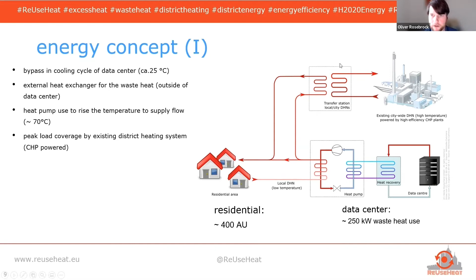If we think about the dimensioning of this heat pump, it was said that it makes sense to cover the base load, and for this it makes sense to have roughly 250 kilowatts of heat recovery, and then a heat pump that delivers 380 kilowatts. So two good sources: the waste heat as the base load, and the existing district heating network as the peak coverage. If we talk about how much area is supplied, we're talking about 48,000 square meters. This low temperature network has roughly 2.8 kilometers in length. We have a 600 or nearly 700 meter connection to the district heating network. You've seen this. It was in the south of the new district.